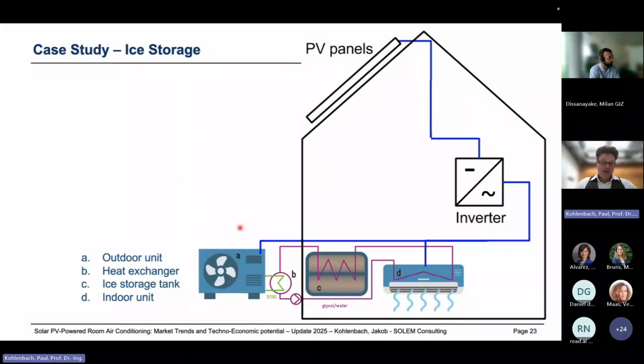Let's start from left to right. We have a conventional outdoor unit here, which is powered by PV electricity. This outdoor unit would normally be connected straight to the indoor unit, which is labeled with a small d here. But in our case, we have connected an ice storage tank in between. And the idea here is to run the indoor unit at nighttime on stored energy from the ice storage.